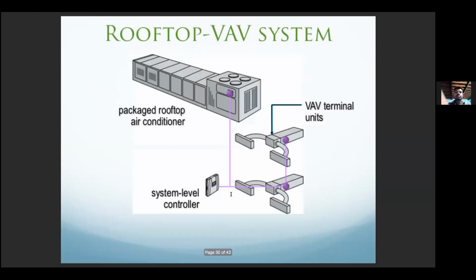Now, rooftop VAV system. We briefly touched on this a few slides ago. There are these VAV terminals that have a controller, and the rooftop has a controller as well. If there were no system controller, the rooftop is told, okay, dump air into the building. The rooftop is a fan that just keeps pumping air into the building. VAV boxes are going to open and close only based on space temperature. Now, if the space is not satisfied, there's no way for the air handling unit to know when to turn off, when to turn on, or whether to increase or decrease the speed of the fan without any input from how the VAV boxes are doing.